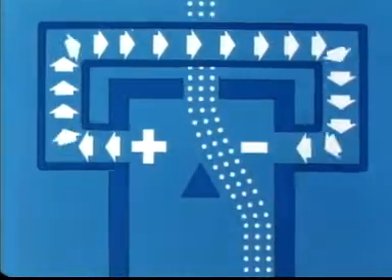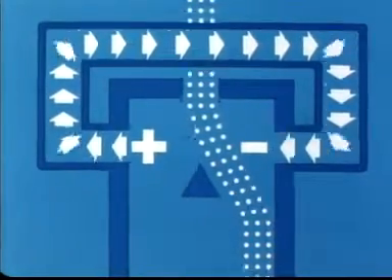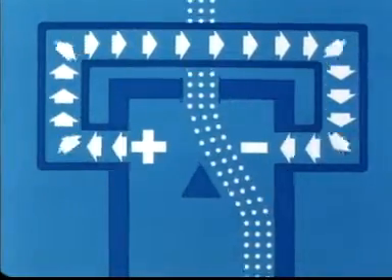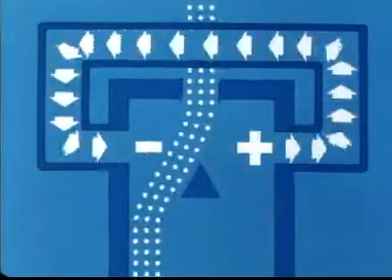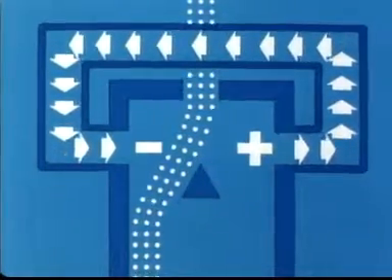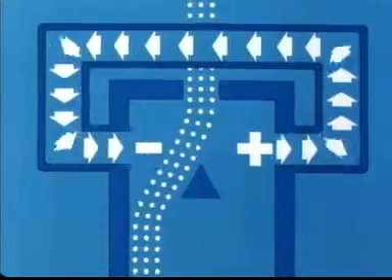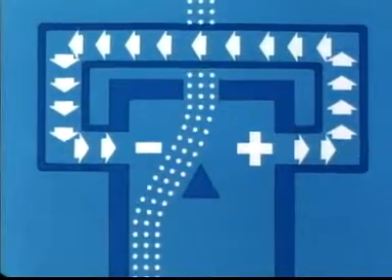The frequency of oscillation is proportional to the velocity of flow. Every pulse represents a specific volume of fluid flowing through the meter. Since the fluidistor consists of fluid passages and has no moving parts, there's nothing that can sustain wear, and the meter is always accurate.